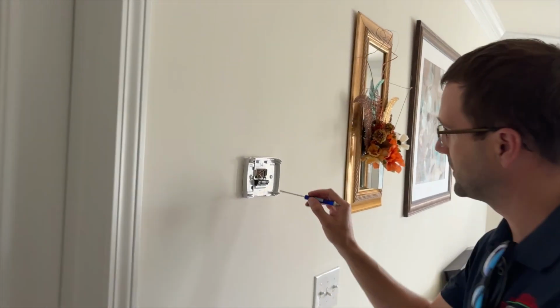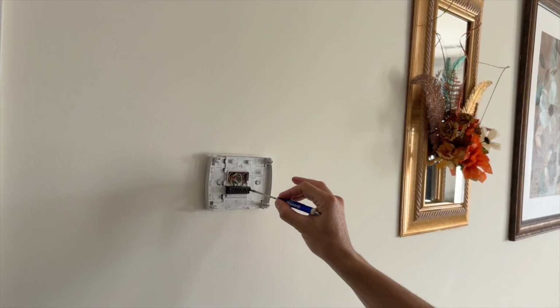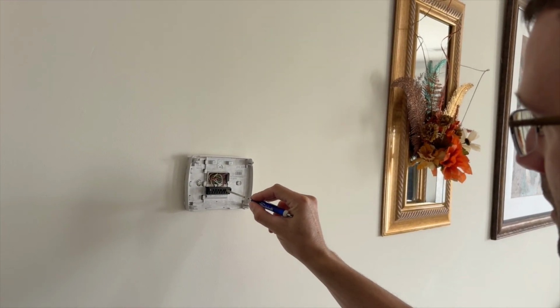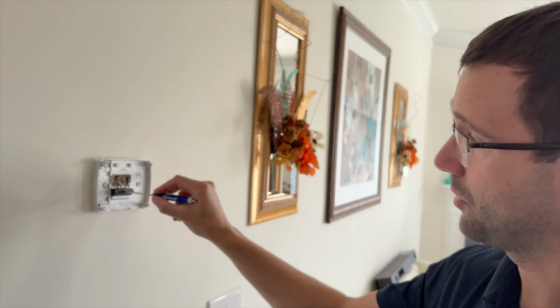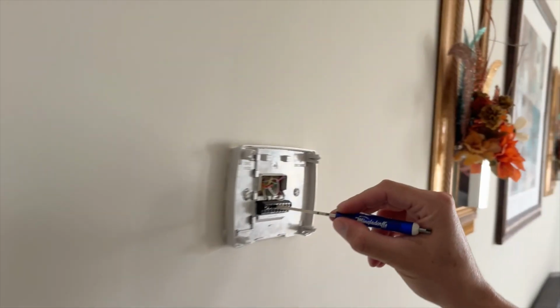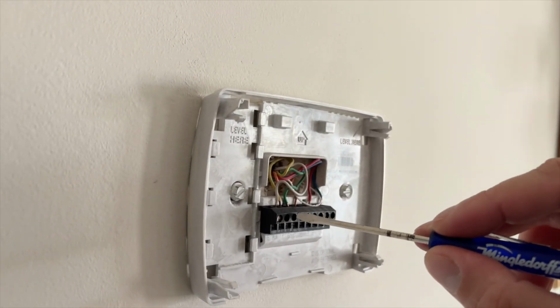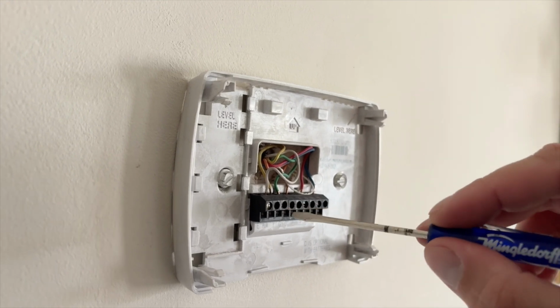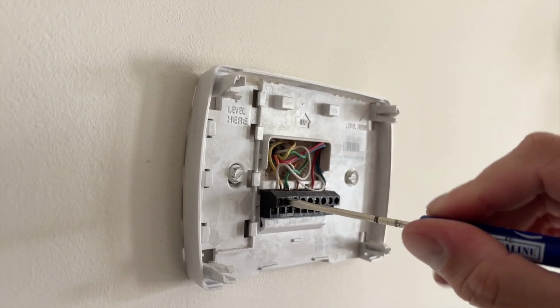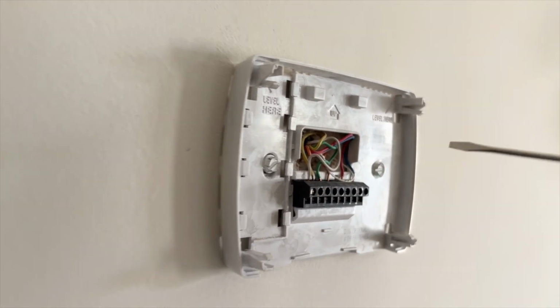So we got our wires in here. We got a common, we got a red, we got an O, which is orange, for our reversing valve. We got a green wire here, that's going to be for our fan. We got a yellow wire here, that's for our compressor. And then we have a white wire here, which is for our emergency or auxiliary heat.